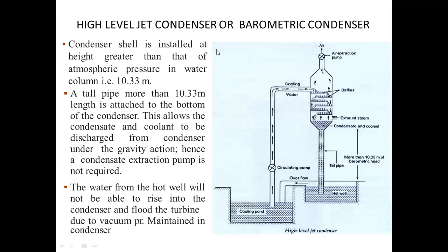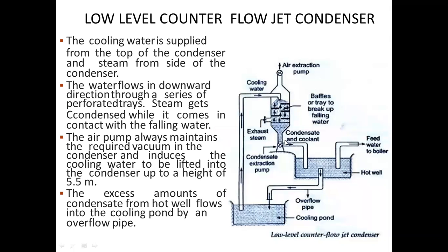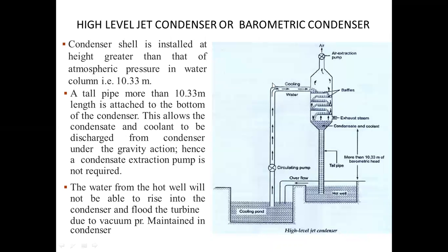Now we discuss the high level jet condenser. High level jet condenser means the length of this pipe is more than the barometric head, that is 10.33 meter. The purpose of increasing the height is to remove the condensate extraction pump which we used here. In case of a low level jet condenser, we use a condensate extraction pump to remove the condensate, while in a high level jet condenser we do not use any pump. Water comes down with the help of gravity only.